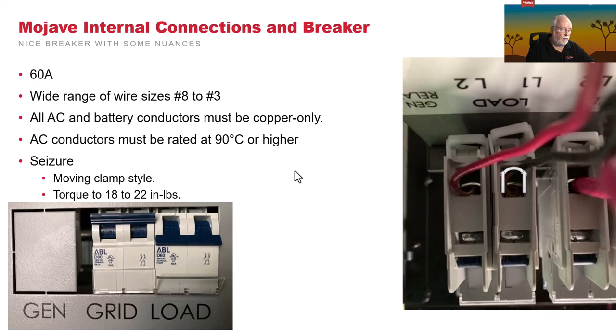And our seizure is a little different. We have what's called a moving clamp style. So if you look over here at the breaker, you'll see this white outline, which kind of shows this silver device that would be moving. So when you tighten the screw, this is actually what happens. You're going to bring that in on the wire. Now this is a look from the underside up. Now that may look like a lot of fun, but it's not. So they're not like the general typical breakers that you're used to using.